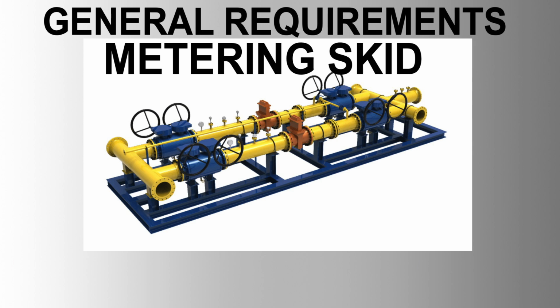3. Service and vendor requirements. Service. Instruments should be designed for ease of servicing, with clear labeling and documentation for each component. All instruments must be fitted with vent and drain facilities, with hazardous fluids being piped to appropriate drainage networks.